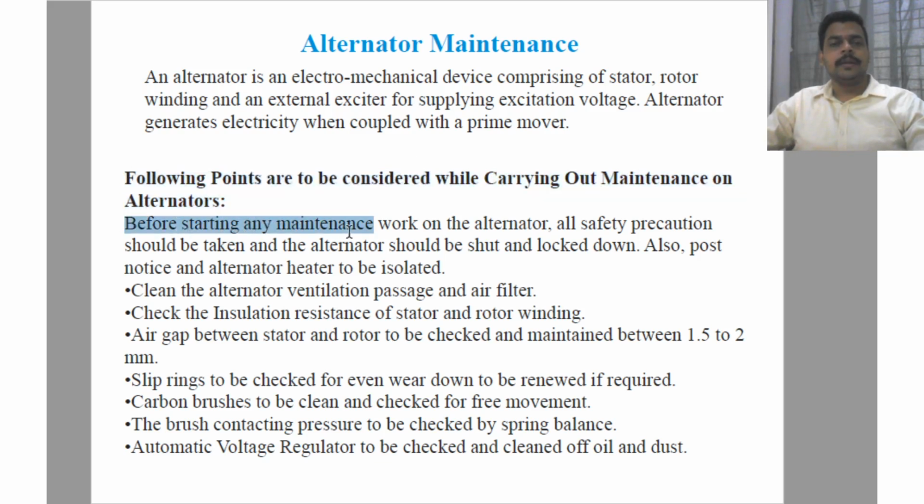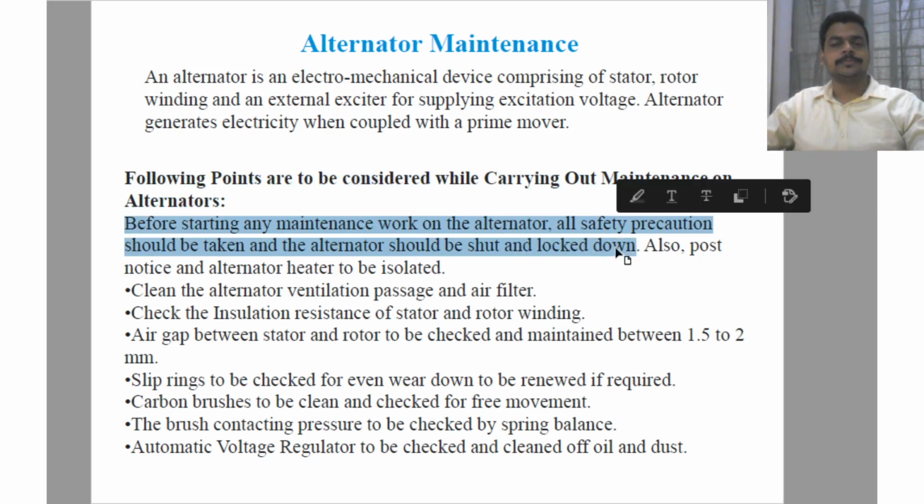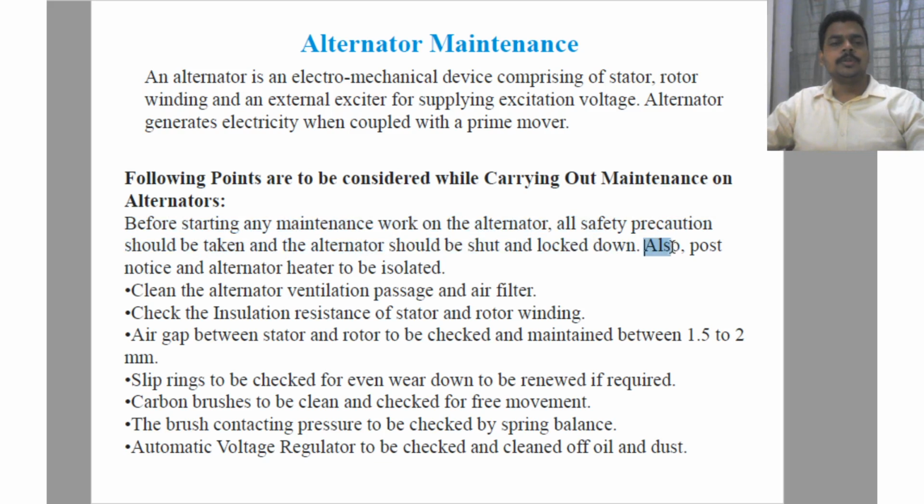Before starting any maintenance work on the alternator, all the safety precautions should be taken and the alternator should be shut down and locked down. Also, post a notice and the alternator heater is to be isolated. This is the prerequisite to do the maintenance. Then we have to clean the alternator ventilation passage and air filter. Check the insulation resistance of stator and rotor winding.